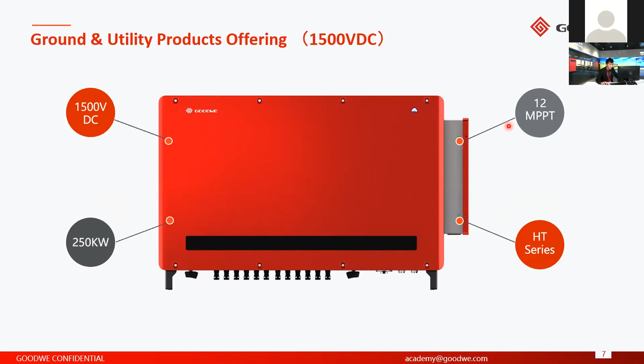Okay, let's go to the features. The first one is the more generation. For the HT series, as I already mentioned, the maximum we can have is 12 MPPT trackers. So it's very suitable for the mounting system. For example, if your panels are installed in the mountain, with a lot of trees and different orientations, different angles of the panels, then in this application scenario, you must use the inverter with multiple MPPT trackers.